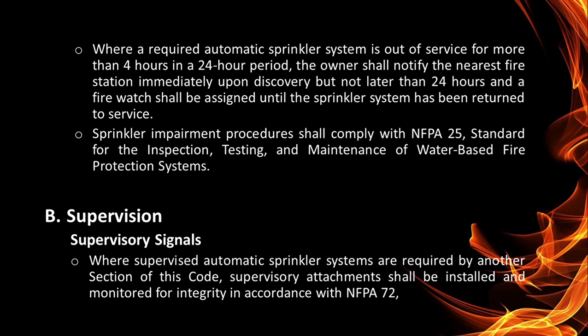Where a required automatic sprinkler system is out of service for more than 4 hours in a 24-hour period, the owner shall notify the nearest station immediately upon discovery but not later than 24 hours, and a fire watch shall be assigned until the sprinkler system has been returned to service. Sprinkler impairment procedures shall comply with NFPA 25, standard for the inspection, testing, and maintenance of water-based fire protection systems.